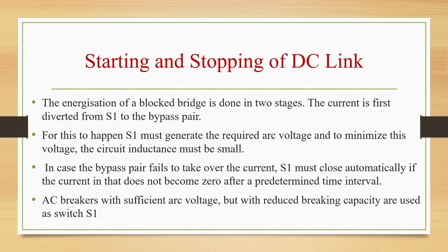AC breakers with sufficient arc voltage but with reduced breaking capacity are used as switch S1. In the second stage of energization, current is diverted from the bypass pair. For the rectifier, this can take place instantaneously, neglecting overlap. Voltage waveforms for this case are shown in the figure below. So the voltage waveform during energization for rectifier and inverter is shown here.